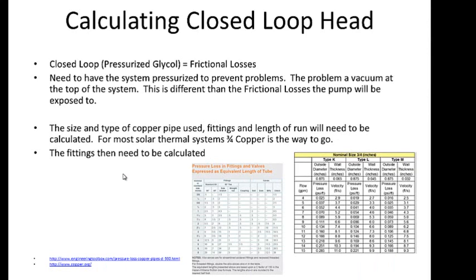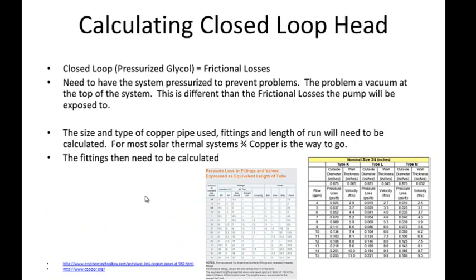Now let's calculate how much loss we have to overcome to get that fluid flowing. Using the Stiebel Eltron system, we have 1.3 gallons per minute to flow. In a closed loop system, we don't have to worry about the height of the system because it's closed and pressurized, so we can use a much smaller pump compared to a drain back, which would require a much heavier duty system. Copper.org has their Copper Pipe Handbook, and the Engineering Toolbox has a nice website linked here, giving us data to calculate fluid flows and head losses.